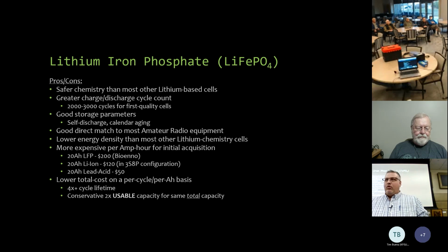They do end up more expensive, quite a bit more expensive than a lead acid battery, for the initial acquisition. But when you factor that out over the total cost on a per cycle, per amp hour basis, they've got about 4 times the cycle life and conservatively about 2 times the usable capacity for the same total nameplate capacity. So the cost per cycle, the cost per amp hour really decreases with lithium iron phosphate batteries compared to lead acid in particular.